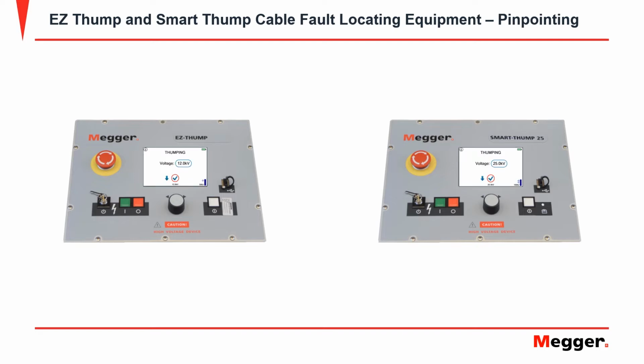Once thumping is selected, you will come to this screen to select a voltage range. You should already know what range you'll be thumping due to the high pot flashover. On the EZ-Thump, the maximum kV is 12 kV with an output of 500 joules or less.